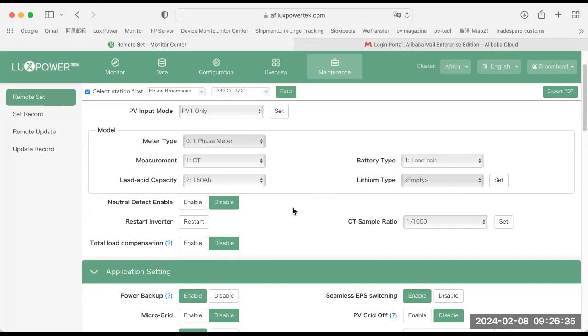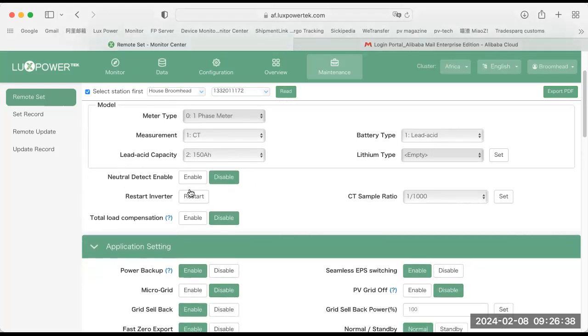And this particular site has a lead acid battery. It's 150 amp hours. So this button here, the neutral detect, is a handy button to have. The feature on the LXP means that it can measure elevated voltage between neutral and earth on the utility supply. Let me explain that. From your municipal feed, it will measure for elevated voltage between neutral and earth. In other words, if you do not have an earth feed coming in, or if there's no bonding from the municipal side, and you enable it, then if the voltage goes above 15 volts on the incoming, the difference in potential between neutral and earth, it will raise an alarm. That's what this particular feature is for. It's very handy.